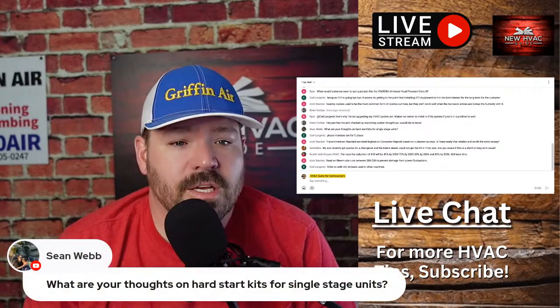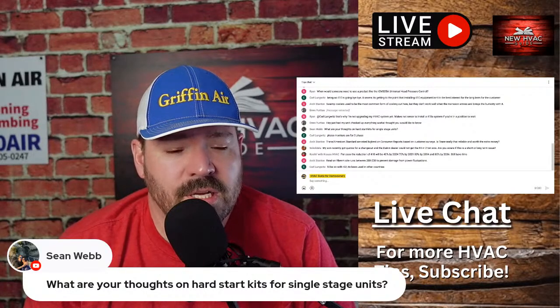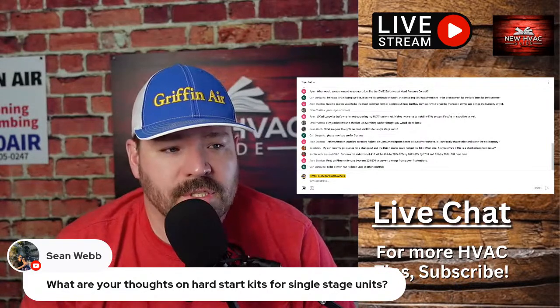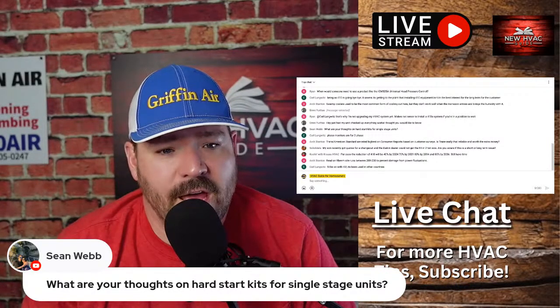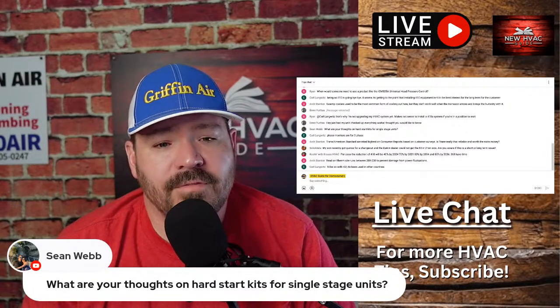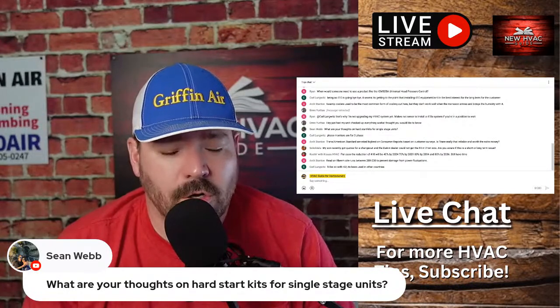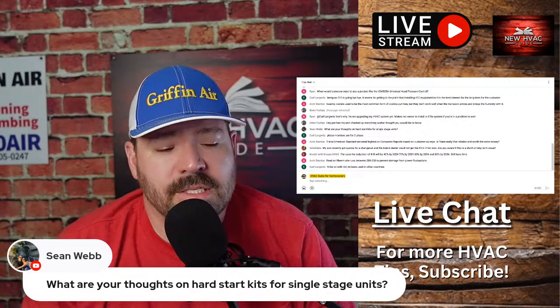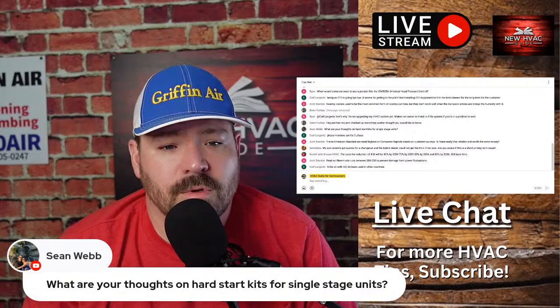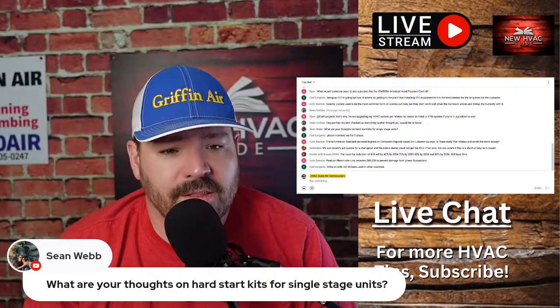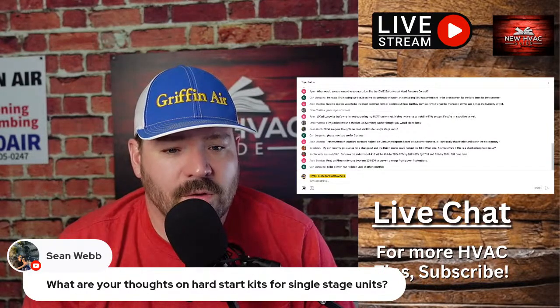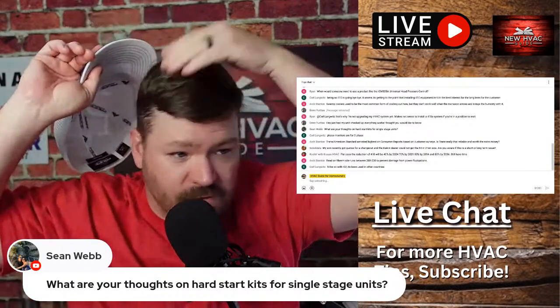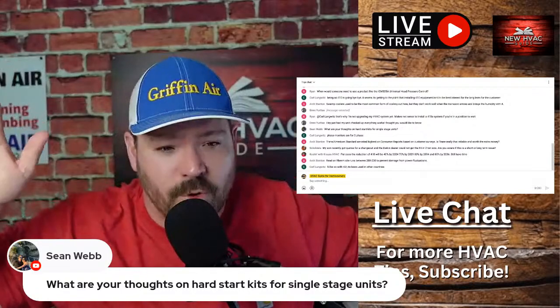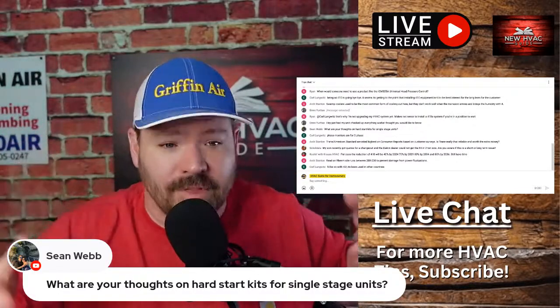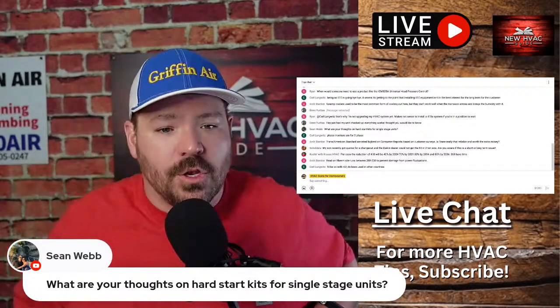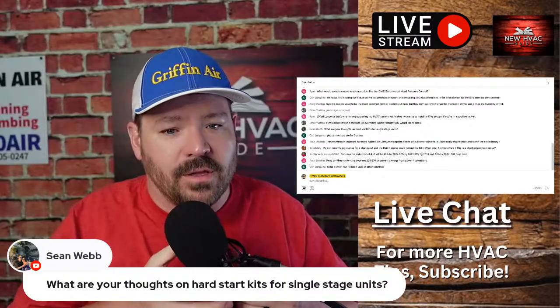Sean says, what are your thoughts on hard start kits for single stage units? I like a hard start kit if it's installed properly and rated right for that unit. I've gotten to where I like a soft start more than a hard start in certain situations. But if that unit is getting older and having a hard time getting rolling, a hard start will buy you some time. In fact, if you're not going to have a soft start, a hard start is good to have, as long as you're not voiding warranties on a new system. Some brands have hard starts on the new system - it comes from the factory that way.